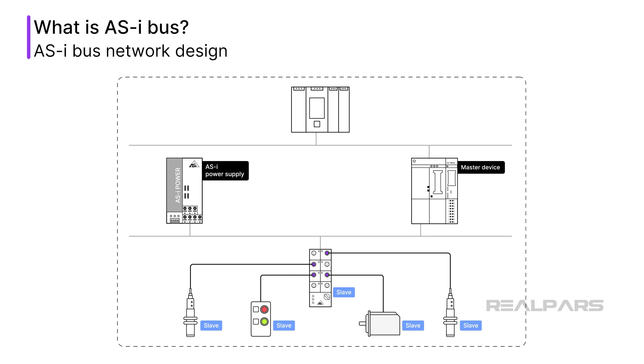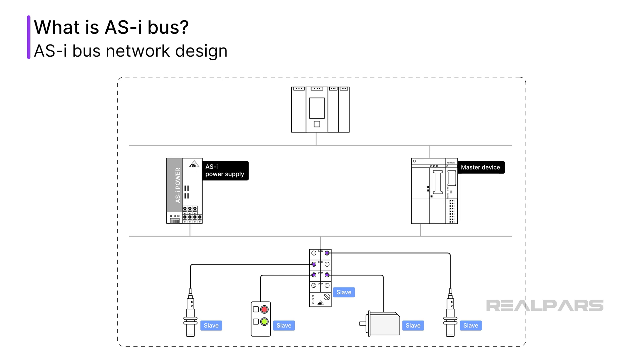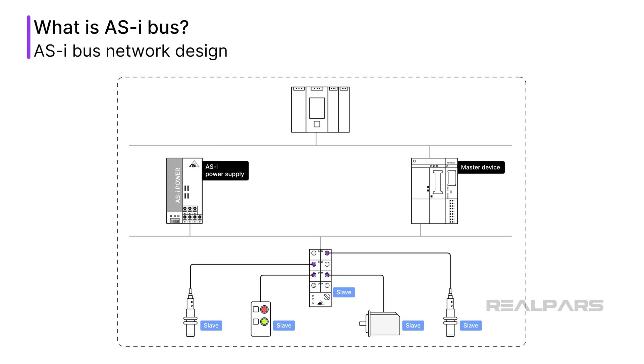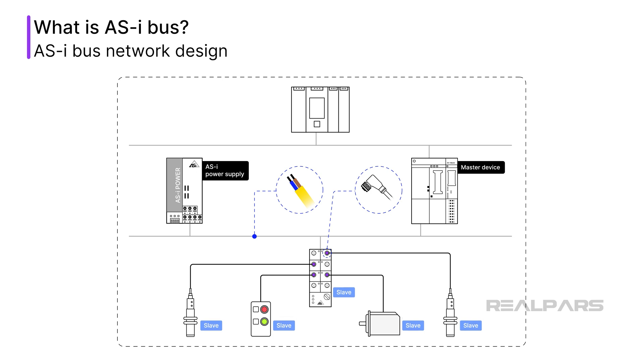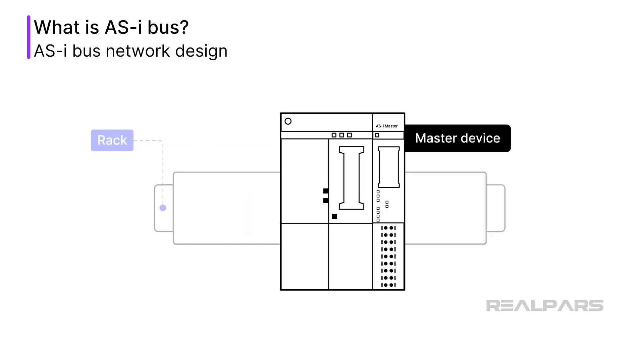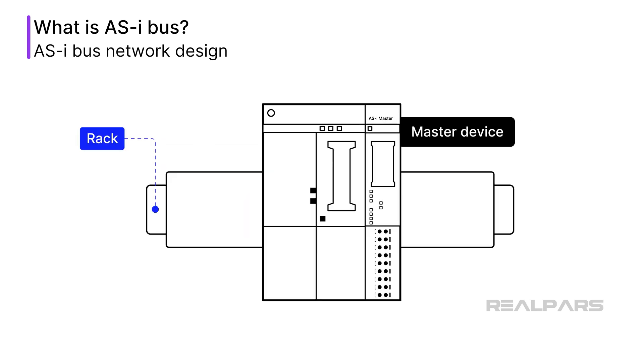An AS-i bus segment requires a master communication module, a power supply, a length of two-wire cable, connectors to attach the various devices, and the devices to which we need to communicate. The master communication module is typically a card that fits into a PLC I/O chassis, or a DCS I/O rack. It has terminals for connecting the power supply and the AS-i bus segment cable.